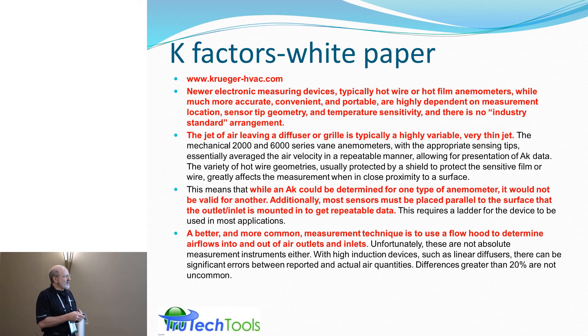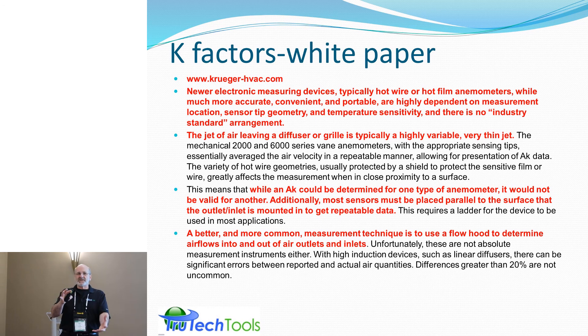On supplies, the jet of air leaving a diffuser or grill can be very highly variable. If you want to demonstrate that, get inexpensive smoke puffers and let students see the airflow coming out of a grill. Grills and diffusers are designed to spread air and create a diffusion pattern to make the room comfortable — but that makes the job of measurement very difficult. So while you can determine AK for one type of anemometer, it wouldn't work for all types. A better measurement is to use a flow hood to determine airflow in and out of outlets.